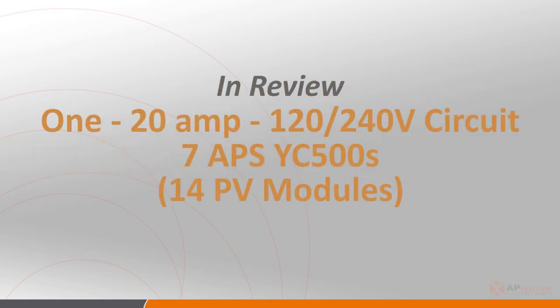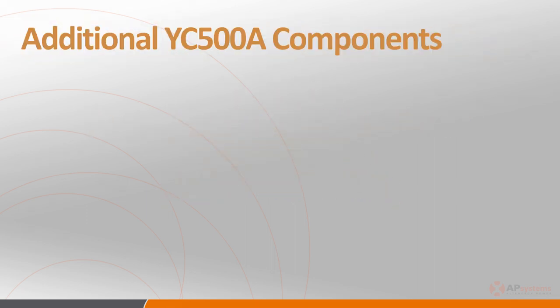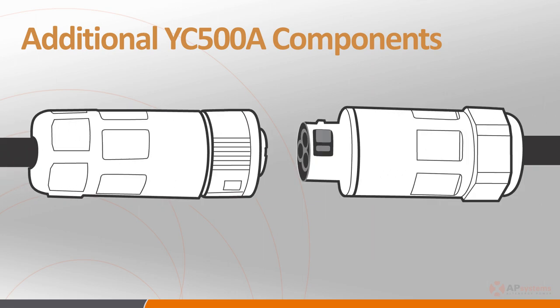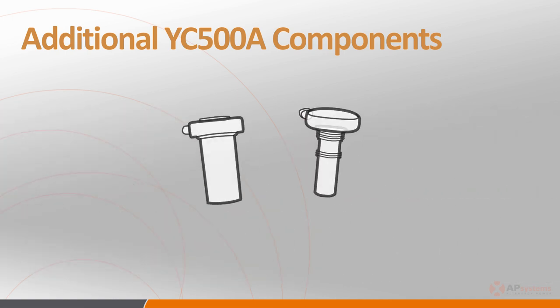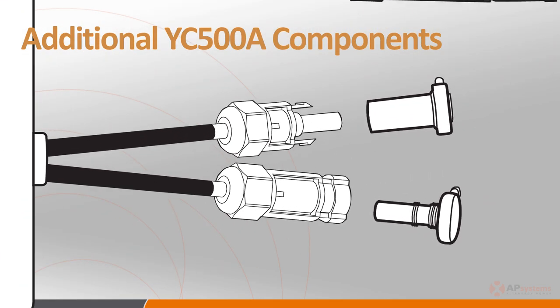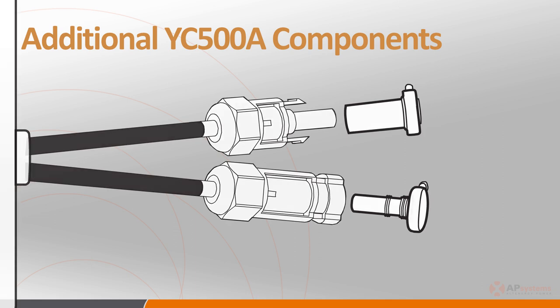As review, the maximum number of units per 120-240 volt 20 amp circuit is 7, or a total of 14 PV modules, and the maximum number of units per a 208 volt 20 amp circuit is 6, or a total of 12 PV modules. Additional components important for a successful YC500A installation are the AC branch cable ends or whips and the end caps. There are also MC4 caps, which are used when only one side of the microinverter will be used, to seal the DC cables on the unused portion. An AC extension cable is also available, which provides extra length to navigate around chimneys or to reach another solar panel installed further than the existing cable allows.